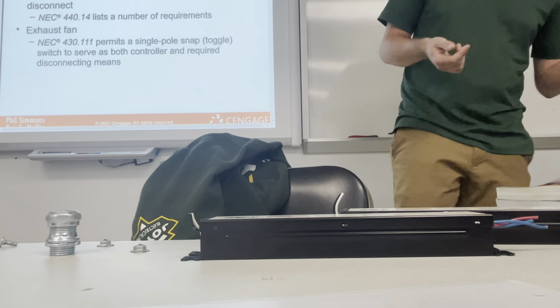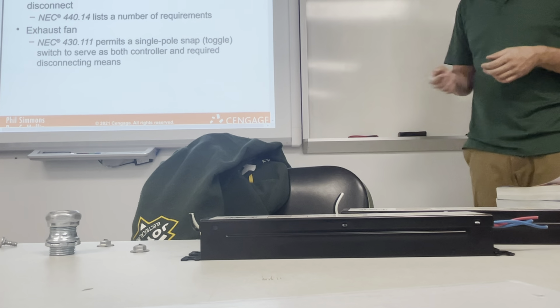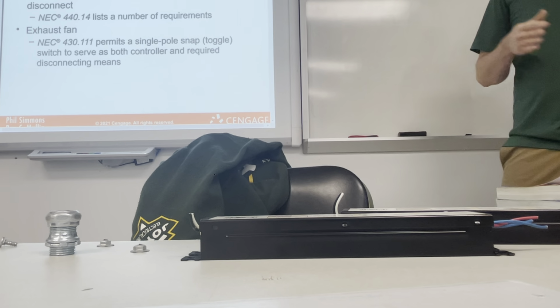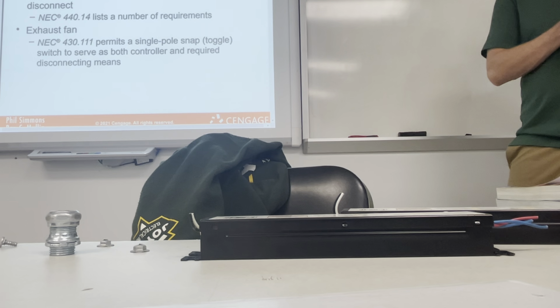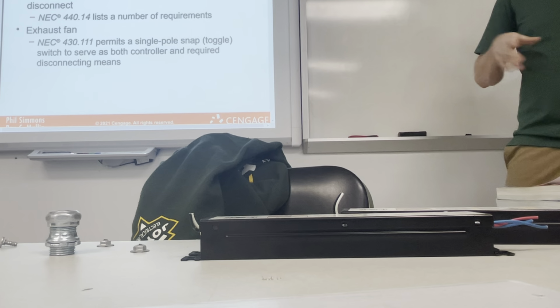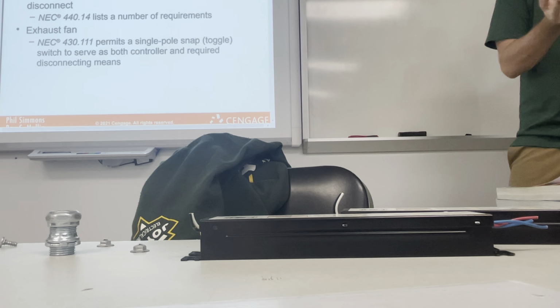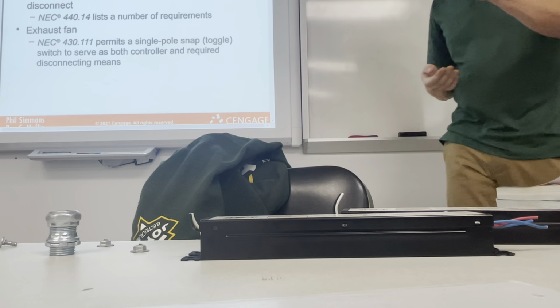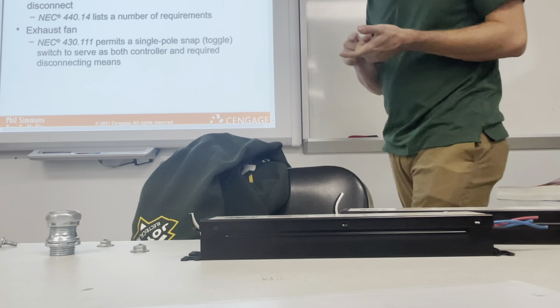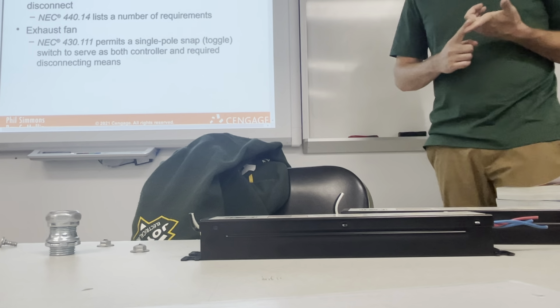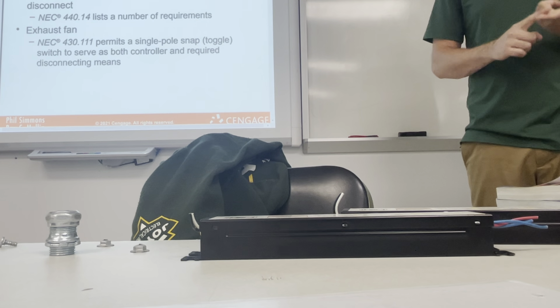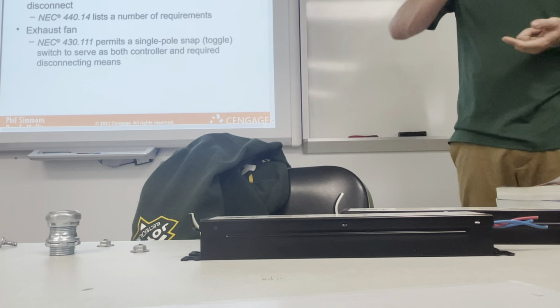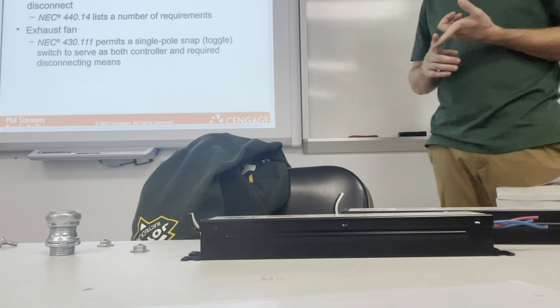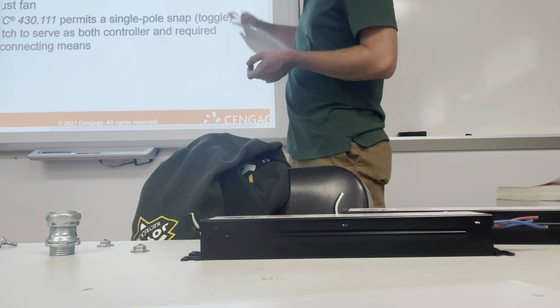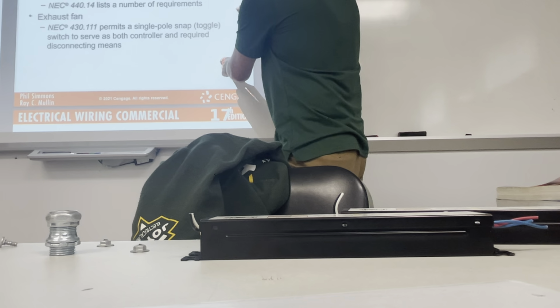Well, there is a 3-pole switch, 3 in, 3 out. That's what you use especially if the exhaust fan is 3-phase, because once again, 3-phase motors do not require a capacitor to start. So it's just the power itself. And if you were to switch legs 1 and 3, that motor would spin in reverse if the motor is rated to go in reverse. Every 3-phase motor can reverse, but only certain ones are rated to actually go in reverse. So if you flip lines 1 and 3, it will spin the wrong direction, which is another basic concept of motor control.